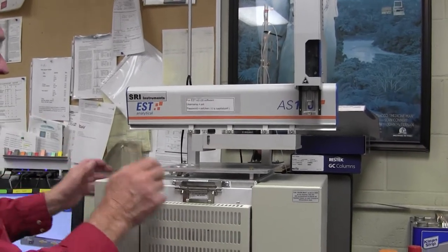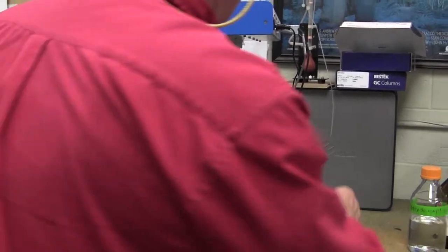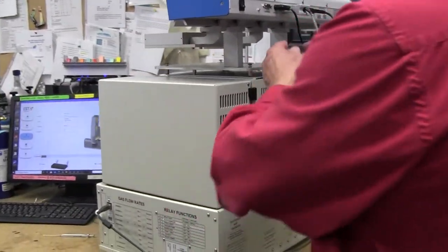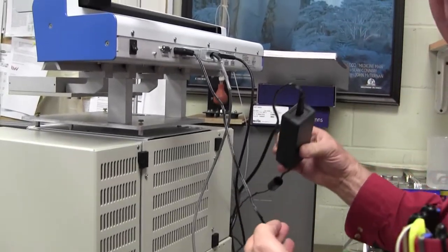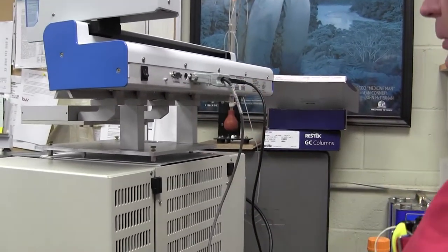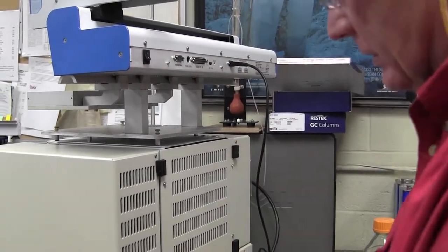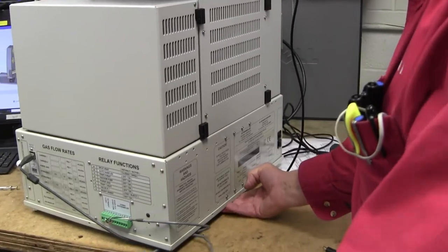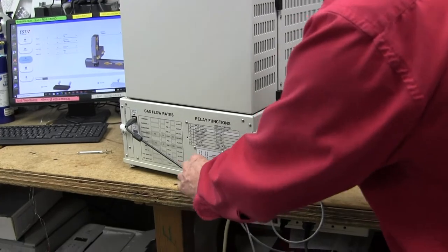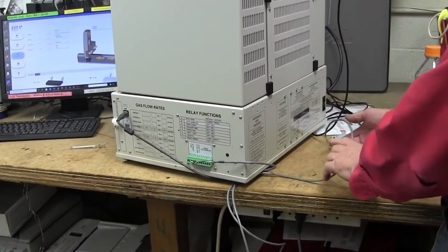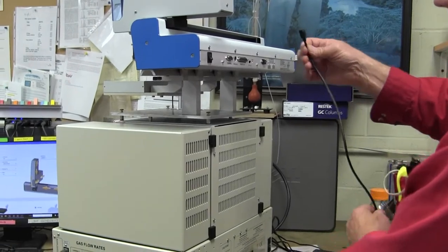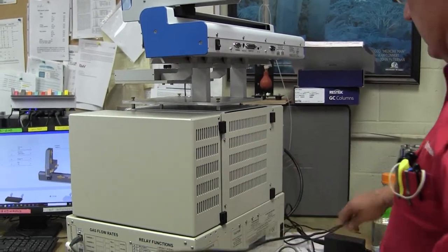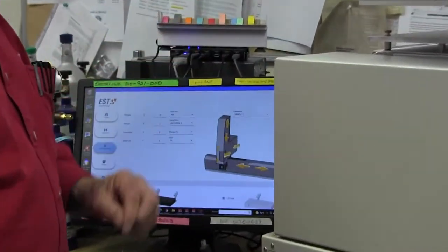So on the back there's a few electrical connections. There's a power which comes from one of these desktop power supplies so we can unplug the power. And then there's this connector which goes to the gas chromatograph. It goes to this plug on the side of the gas chromatograph. This is how the auto sampler and the GC talk. And then there's this which is the USB cable. It's a micro USB on this side but on the side that connects to the computer it's a regular USB cable.